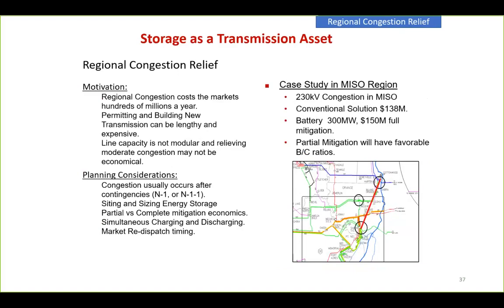Same thing in the Mid-Continent ISO: 230 kV congestion, where full mitigation is too expensive but partial mitigation pencils out. As a side comment, the sub-transmission space is kind of a gap—it has the same N-1 overload avoidance issue, but usually isn't part of the ISO's congestion management and market dispatch because it's below the transmission level. It's not distribution either, but it's where distributed storage can really pay off for utilities.